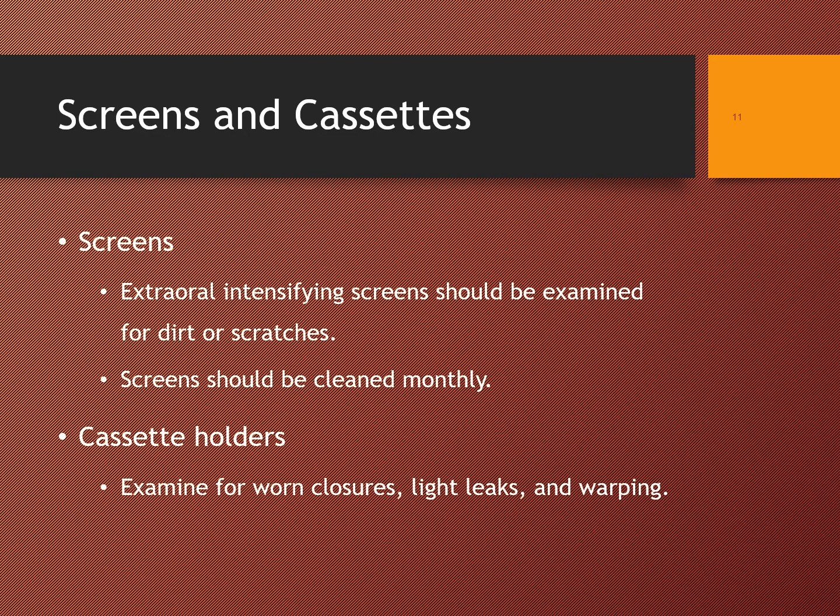But if you had a flexible cassette, obviously it would warp a little bit. A commercial cleaner is usually available in order to clean these cassettes and the screens. You don't want to use just any kind of cleaner whatsoever. Use the one that the manufacturer recommends. And then also, once it's clean, you want to spray it with an anti-static solution so that you won't get that static electricity across any of your radiographs.